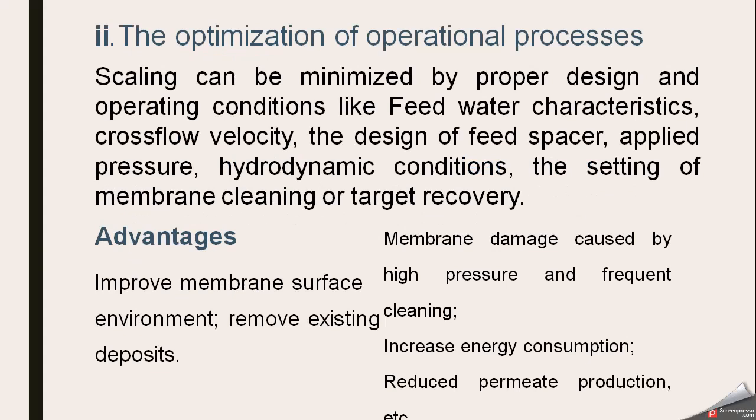The second is the optimization of operational processes. Scaling can be controlled or minimized by proper design and operating conditions like feed water characteristics, cross-flow velocity and feed spacer design, and during the operation we can apply a suitable pressure. We will not apply too much pressure to get more permeate water, so that more scaling will not occur.